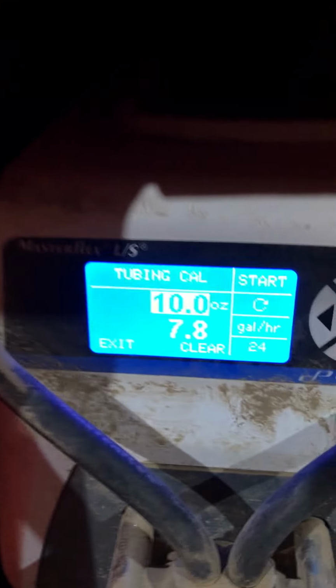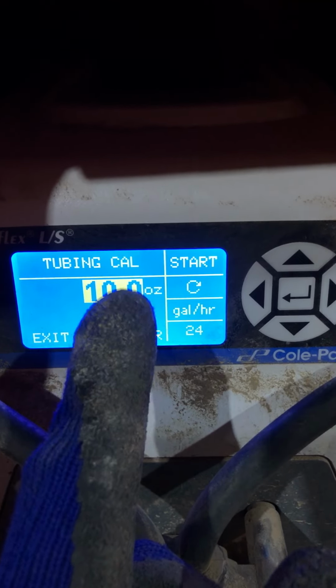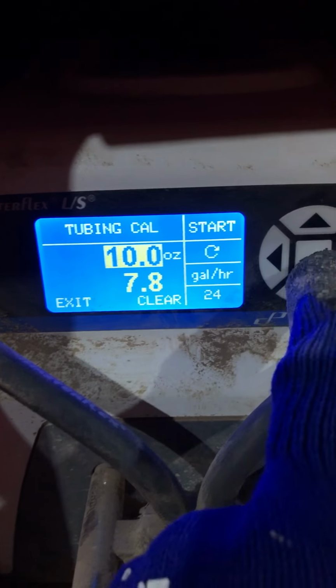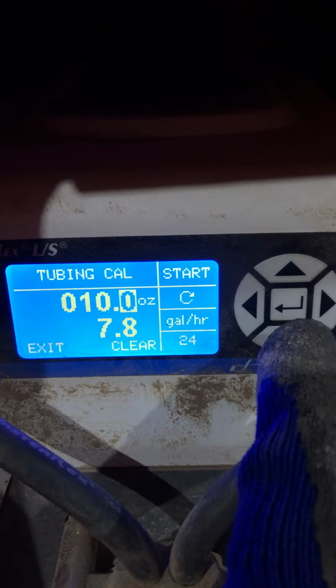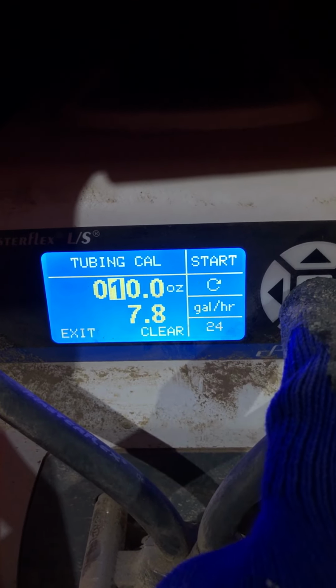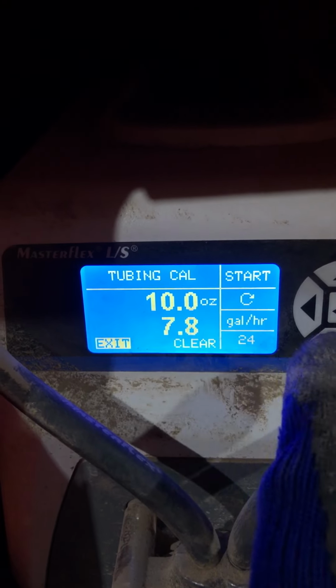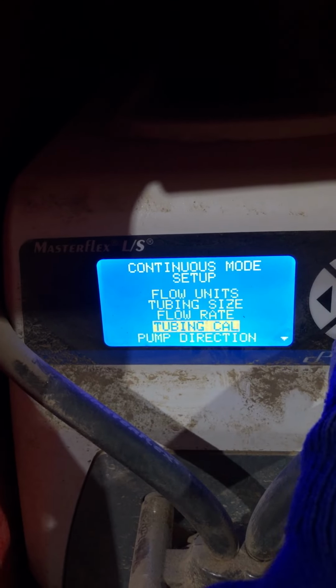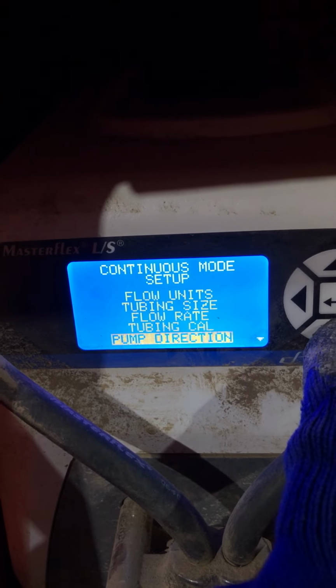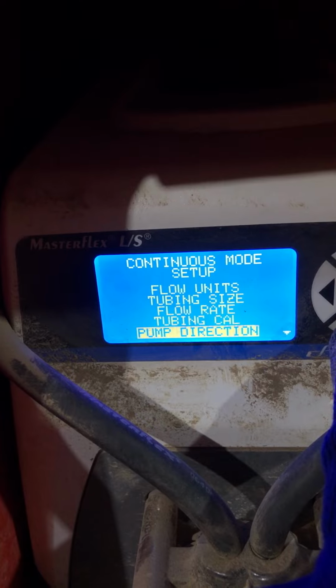So now if you got 9.5, you would edit this number. But now this number is highlighted because it stopped pumping. So if you want to edit, you click enter, change the digits. In our case, we like it. Now you exit. Okay, now you're calibrated. You do that as many times as it takes to get to 10 ounces.